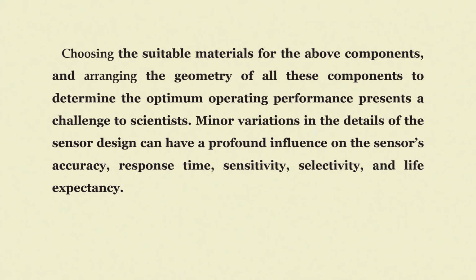Many people may change the design particularly because chemistry is the same. So, from a trade point of view or from the business point of view, it makes sense to change minor components, and that provides for minor variations in the details of the sensor design to have a profound influence on the sensor's accuracy, response time, sensitivity, selectivity, life expectancy, and then quite often we worry about the efficiency also and interferences.